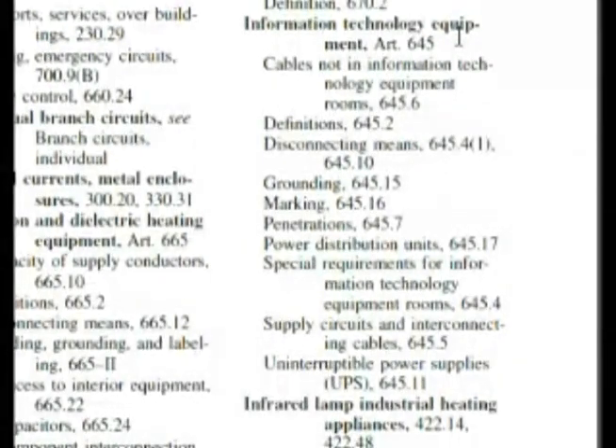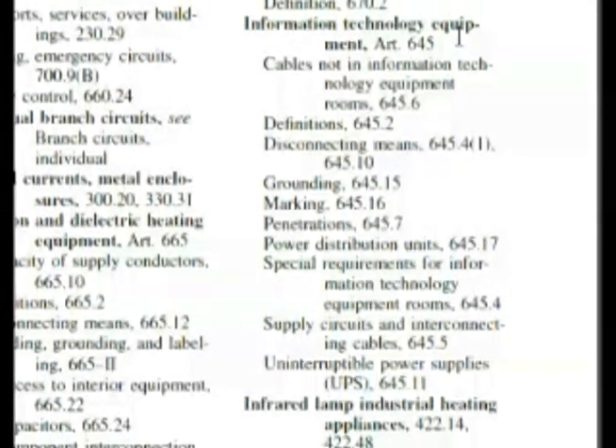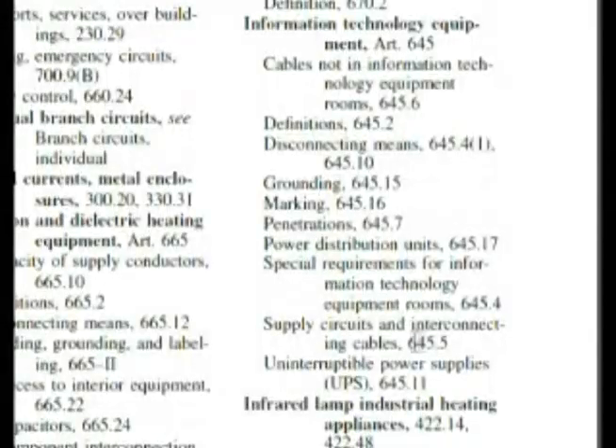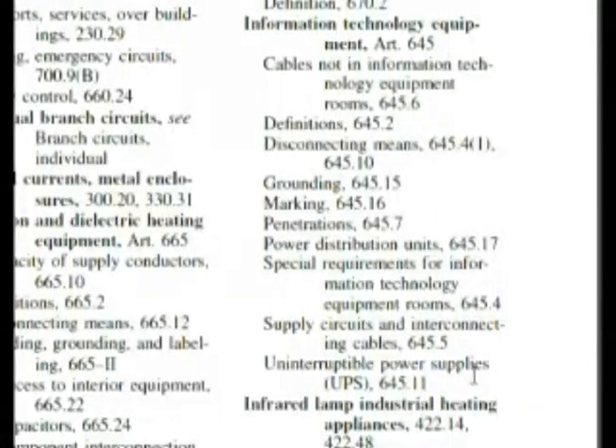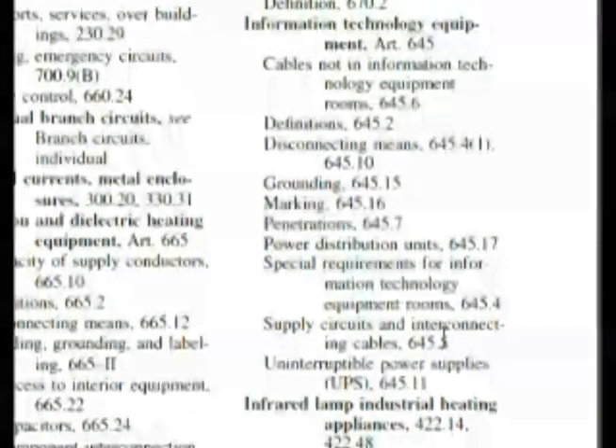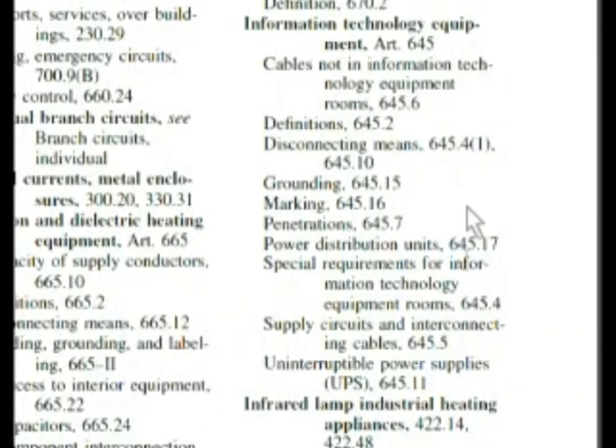The more parts of the code that you know, the faster it's going to help you look things up. Now we have to find something that works under this. It's talking about disconnecting means here — that could be something. And if we come down here to supply circuits and interconnecting cables, that was in our question — it was talking about interconnecting cables. So let's go to 645.5, disconnecting is 645.4(1), and then 645.10. I want to go to interconnecting cables first, simply because that wording was in our question. And if not, we'll be right in the area to check disconnecting means.